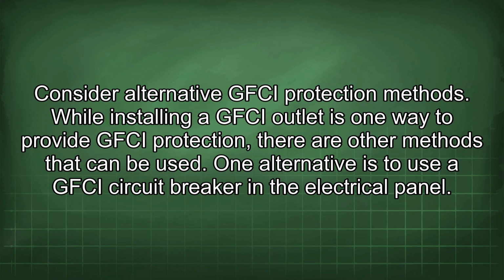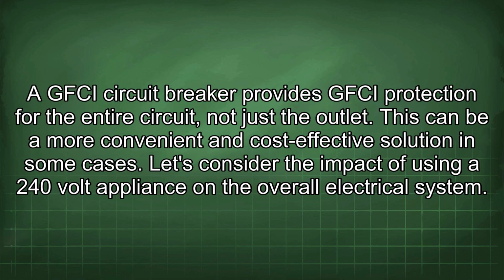Consider alternative GFCI protection methods. While installing a GFCI outlet is one way to provide GFCI protection, there are other methods that can be used. One alternative is to use a GFCI circuit breaker in the electrical panel. A GFCI circuit breaker provides GFCI protection for the entire circuit, not just the outlet. This can be a more convenient and cost-effective solution in some cases.